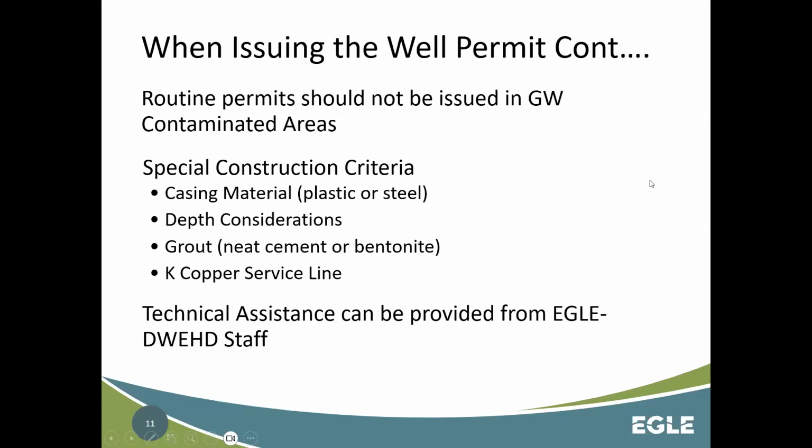Type of grout. We tend to require neat cement in areas of groundwater contamination because that will prevent cross-contamination a little bit better. And K-copper service lines are important if it's a shallow water table and there's contamination in the area. We don't want PVC to be degraded.